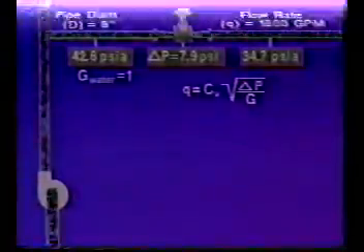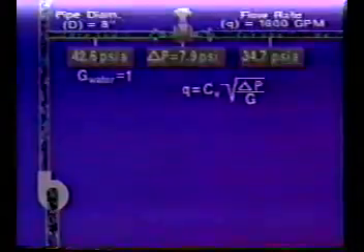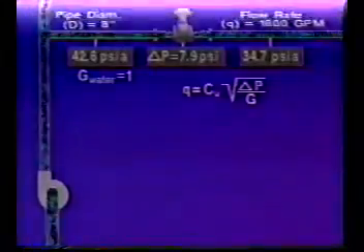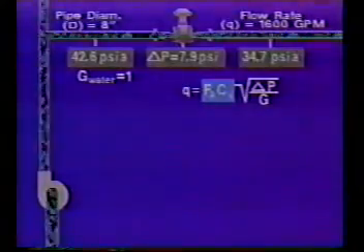The first step is to determine the minimum required flow coefficient. As you may recall, the basic flow rate equation provides a relationship between C sub V and some of our known data. Because we're interested in placing a 6-inch valve in an 8-inch pipe, we need to include the piping geometry factor, F sub P, in the equation. Now, it may be helpful at this point to think of the term F sub P C sub V as the effective flow coefficient for the installation.